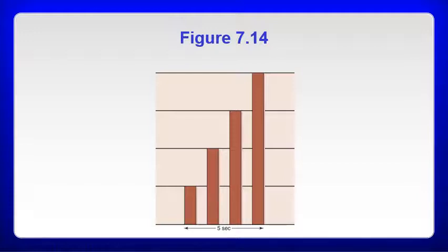The thing you have to keep in mind is that if there's going to be a ramp, they're only going to be at the intensity you want for a certain period of time. We'll talk about setting ramp. It's usually good to do that because it's a little more comfortable for the patient instead of it just turning on and going right up to the intensity. It's a nice gradual lead up to the intensity and a more gradual contraction.